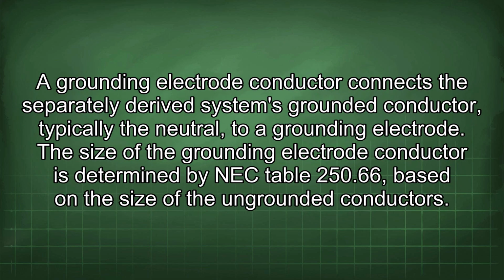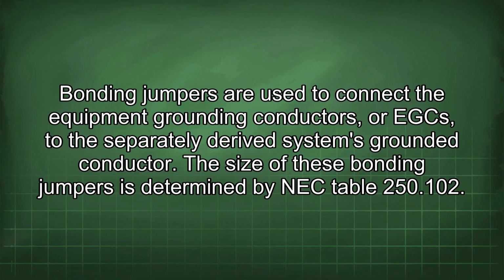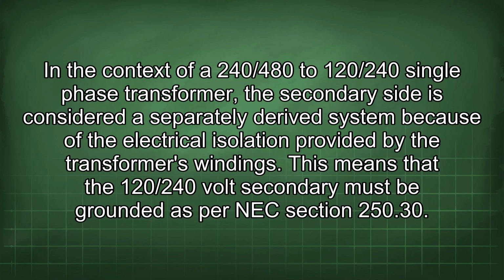A grounding electrode conductor connects the separately derived system's grounded conductor, typically the neutral, to a grounding electrode. The size of the grounding electrode conductor is determined by NEC Table 250.66 based on the size of the ungrounded conductors. Bonding jumpers are used to connect the equipment grounding conductors, or EGCs, to the separately derived system's grounded conductor. The size of these bonding jumpers is determined by NEC Table 250.102.